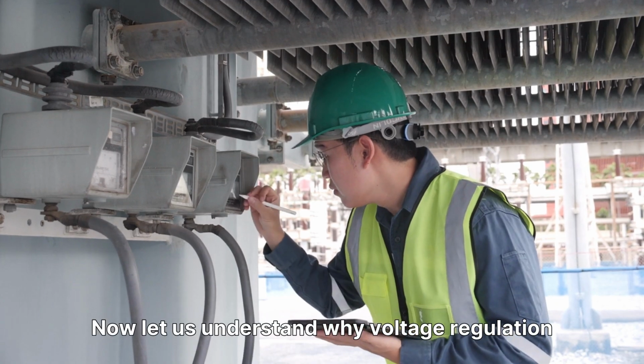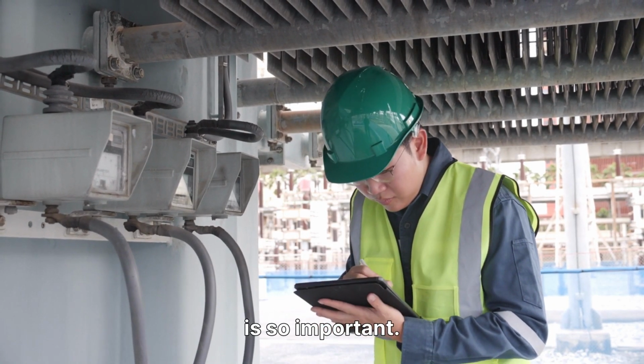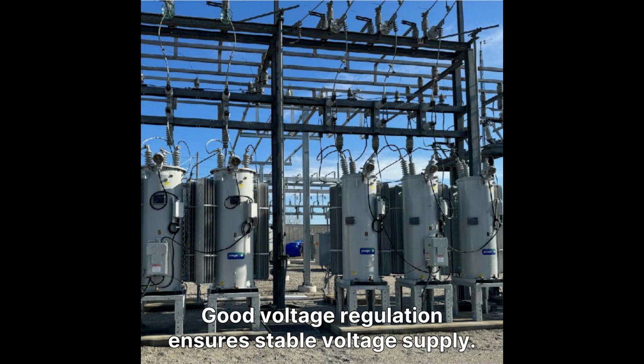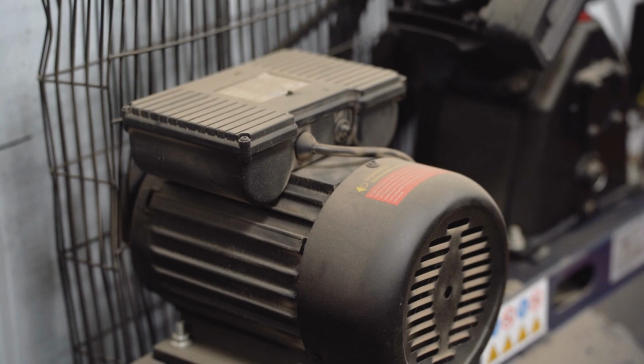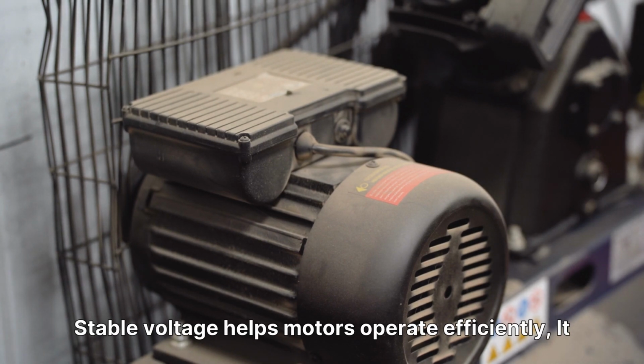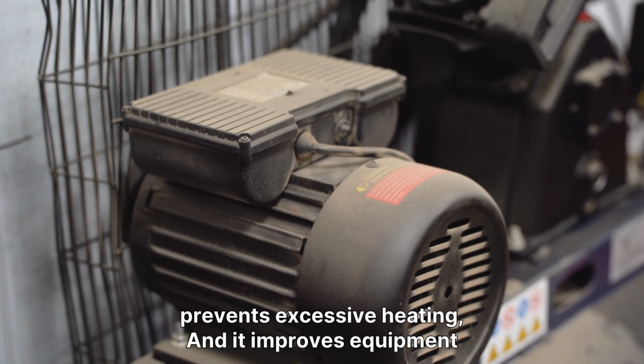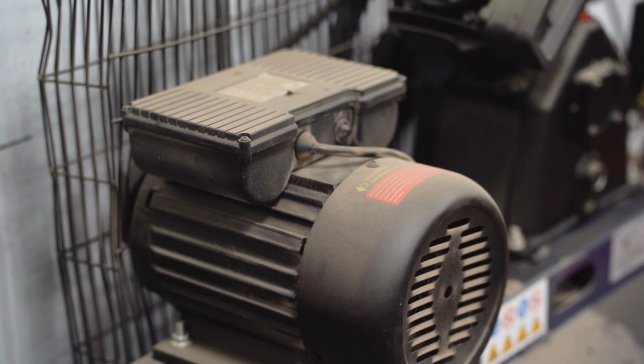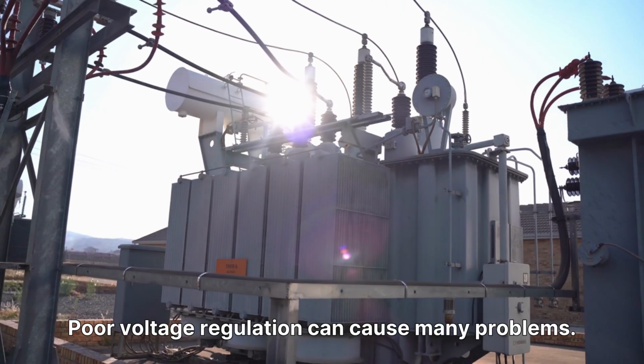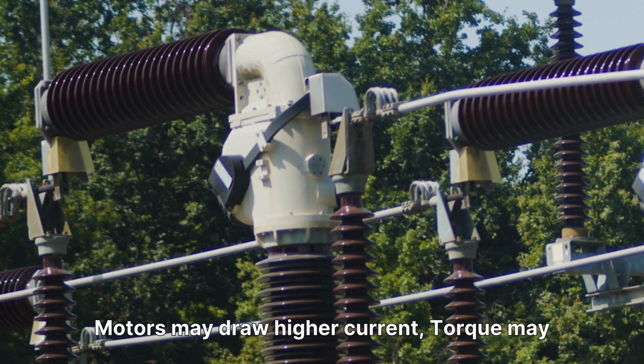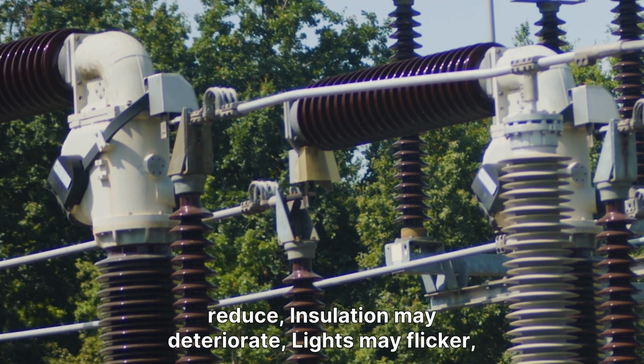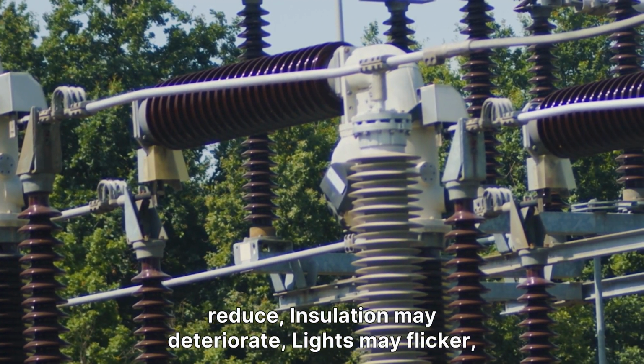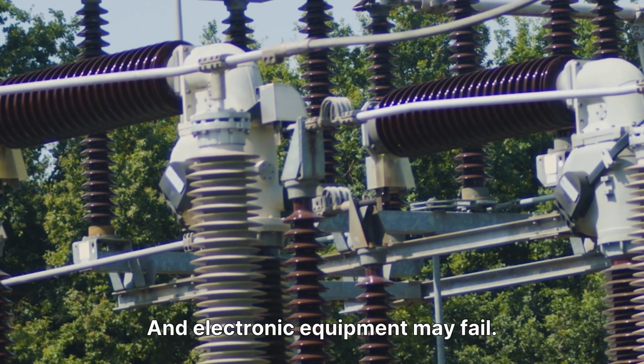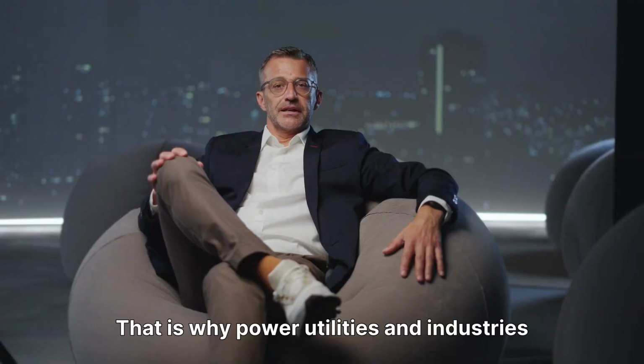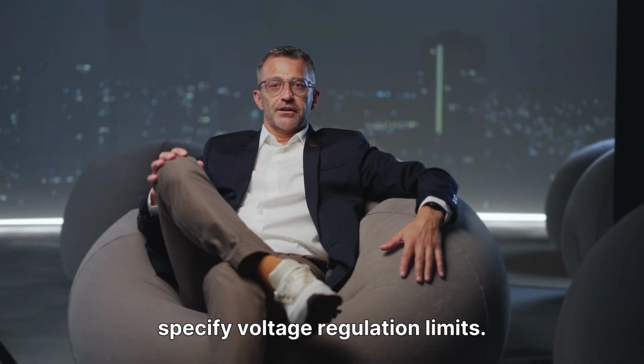Now let us understand why voltage regulation is so important. Good voltage regulation ensures stable voltage supply. Stable voltage helps motors operate efficiently. It prevents excessive heating, and it improves equipment life. Poor voltage regulation can cause many problems. Motors may draw higher current, torque may reduce, insulation may deteriorate, lights may flicker, and electronic equipment may fail. That is why power utilities and industries specify voltage regulation limits.